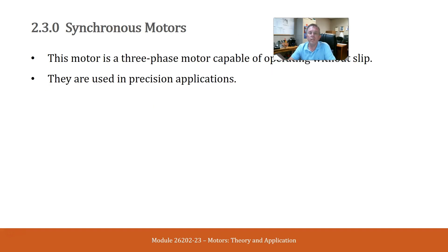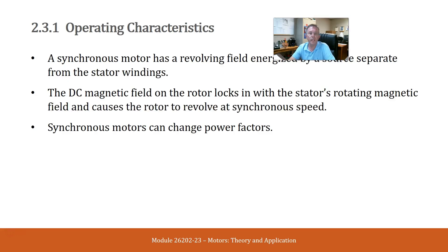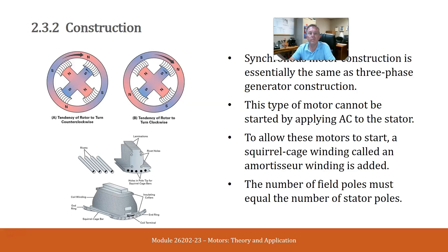This motor is a three-phase motor capable of operating without slip. They are used in precision applications — that's synchronous motors. The synchronous motor has a revolving field energized by a source separate from the stator winding. The DC magnetic field on the rotor locks in with the stator's rotating magnetic field and causes the rotor to revolve at synchronous speed. Synchronous motors can change power factors. Synchronous motor construction is essentially the same as three-phase generator construction. This type of motor cannot be started by applying AC to the stator. To allow these motors to start, a squirrel cage winding called an amortisseur winding is added.